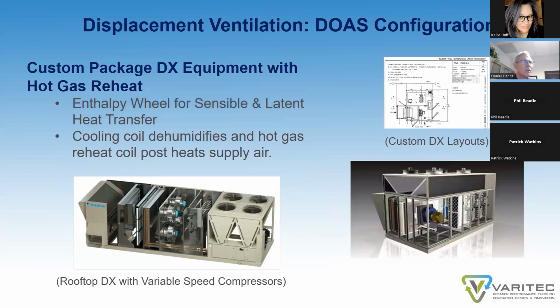Another solution that should be given every consideration, in my opinion, is looking at a custom packaged DX solution. Now with our variable speed compressor technology, our ability to modulate refrigerant flow based on demand, the capacities to provide suppressed dew points of 48 degrees, 46 degrees, make this a very attractive option for future building designs.